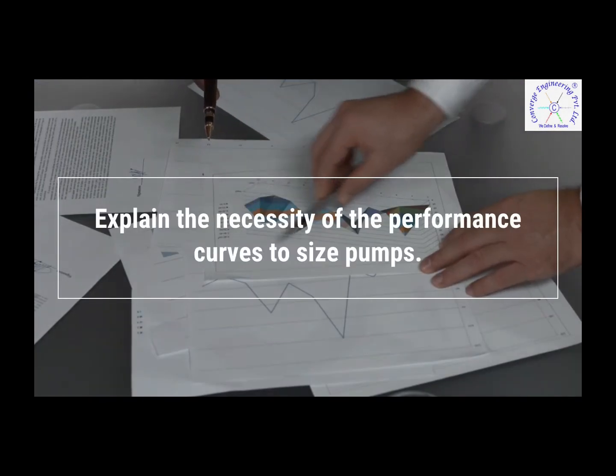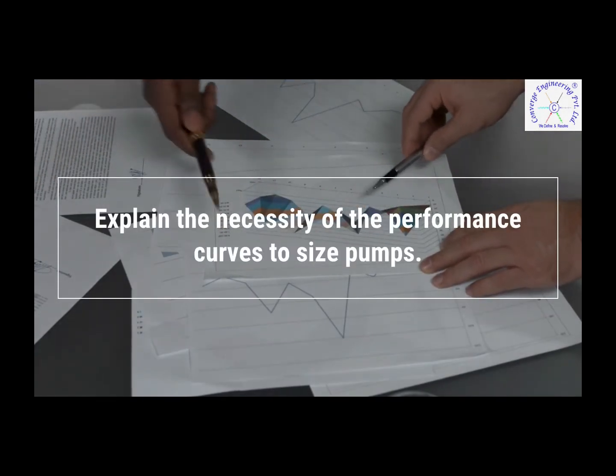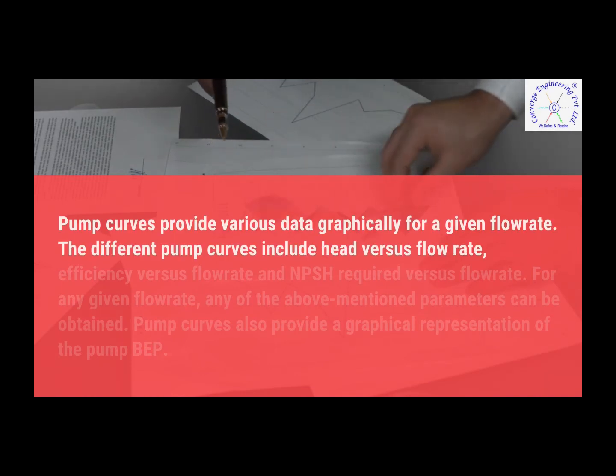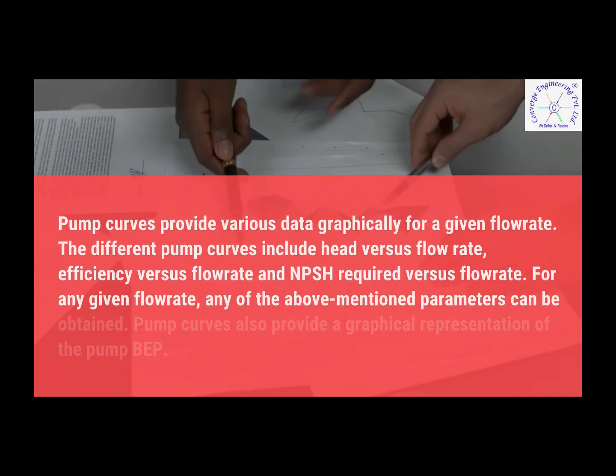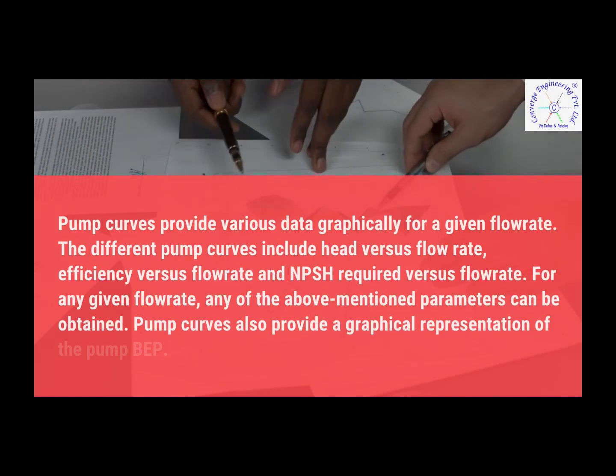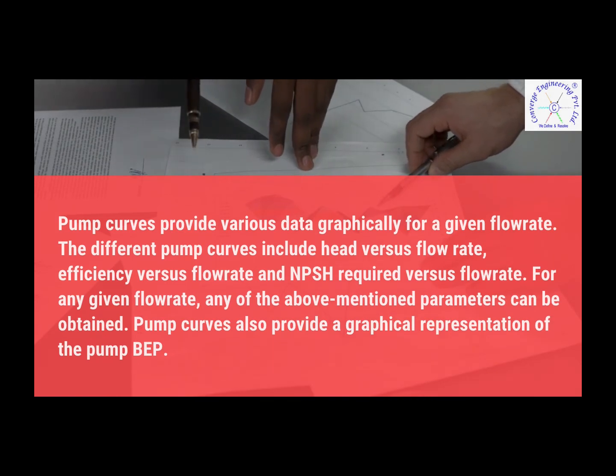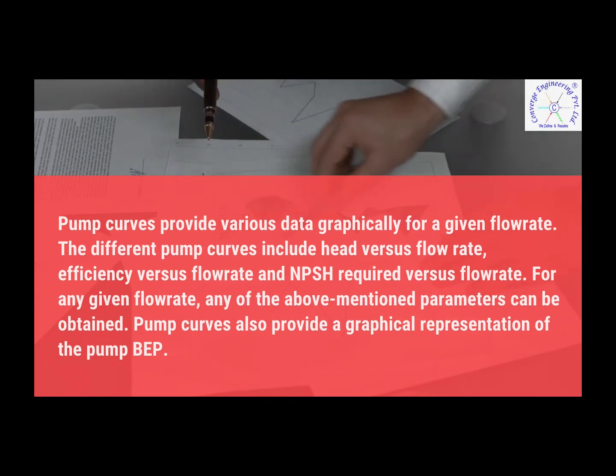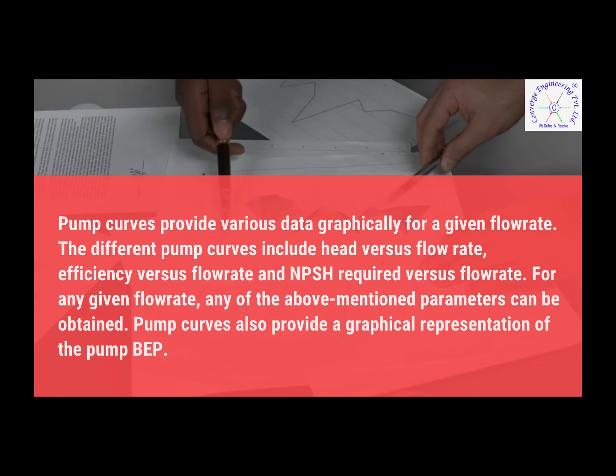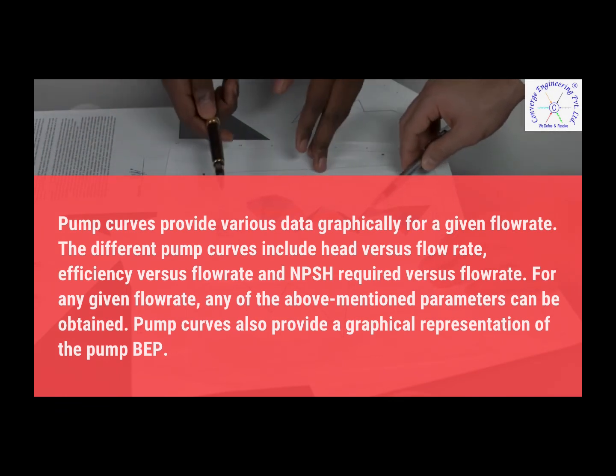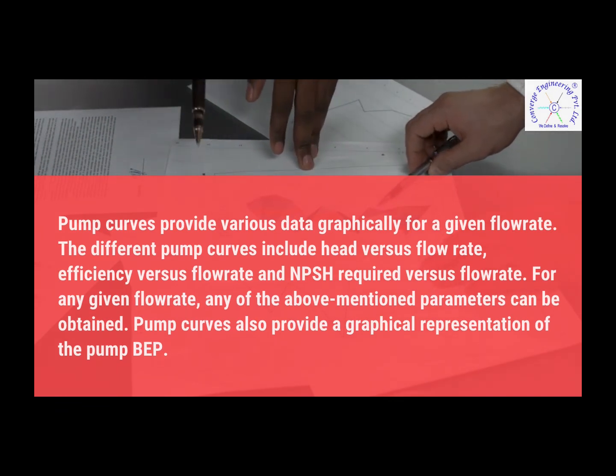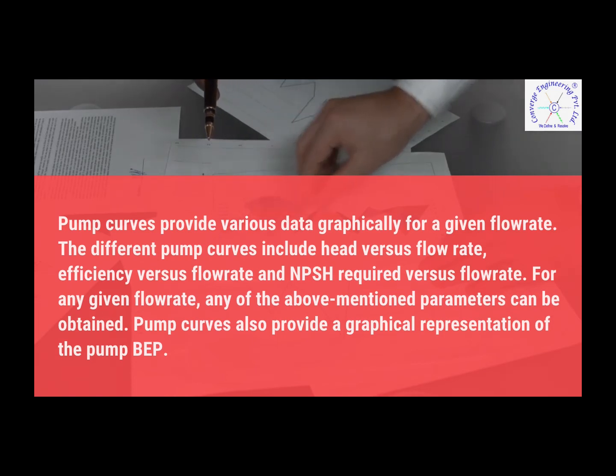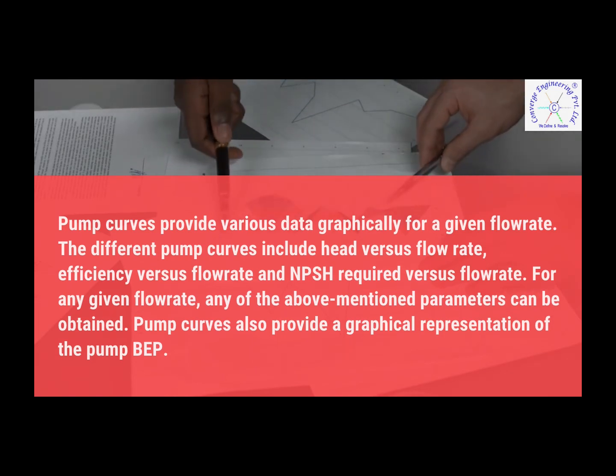Explain the necessity of performance curves to size pumps. Pump curves provide various data graphically for a given flow rate. The different pump curves include head vs. flow rate, efficiency vs. flow rate, and NPSH required vs. flow rate. For any given flow rate, any of these parameters can be obtained. Pump curves also provide a graphical representation of the pump's BEP (best efficiency point).